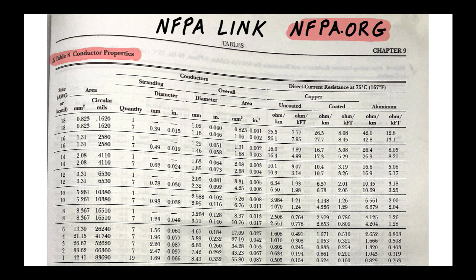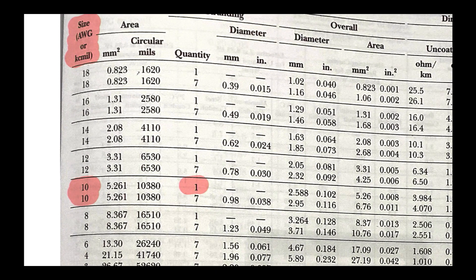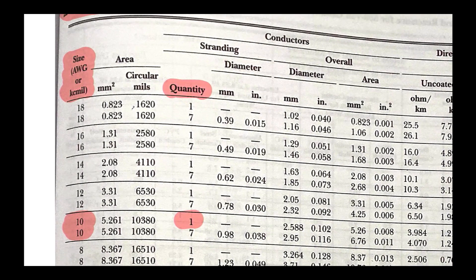We're going to find 10 AWG, and we see it listed twice. Let me zoom in so you can see — it's listed twice. Over here we have a number 1 and a number 7: number 1 means solid, number 7 means stranded with seven strands. Since we're looking for solid, we look at number 1 in the column called 'Quantity.' It's actually easy once you understand how it's structured.